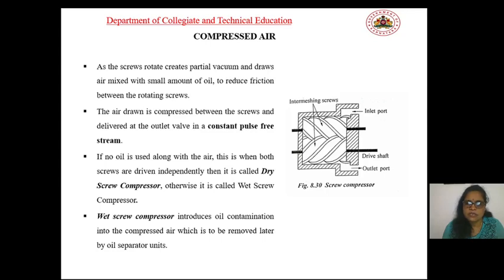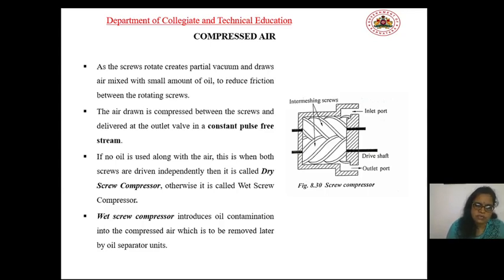If no oil is used and both screws are driven independently, it is called a dry screw compressor; otherwise it is called a wet screw compressor. In dry screw compressors, the screws are driven independently. In wet screw compressors, a small amount of oil is used, which introduces oil contamination into the compressed air that must be removed later by an oil separator.